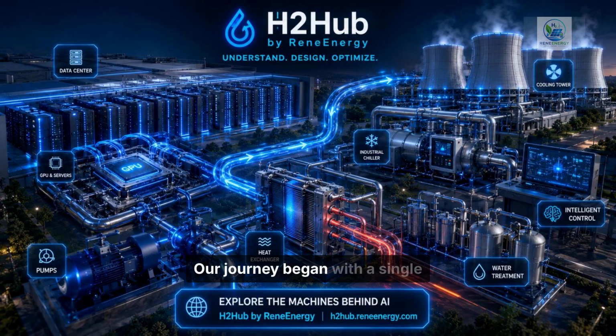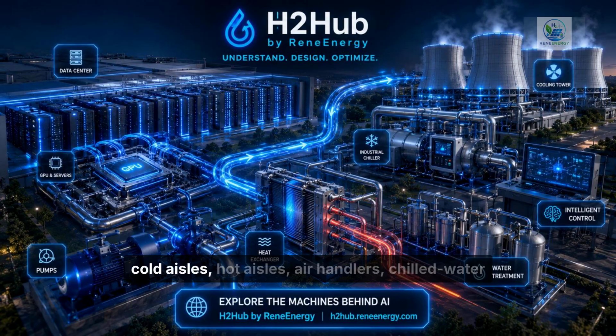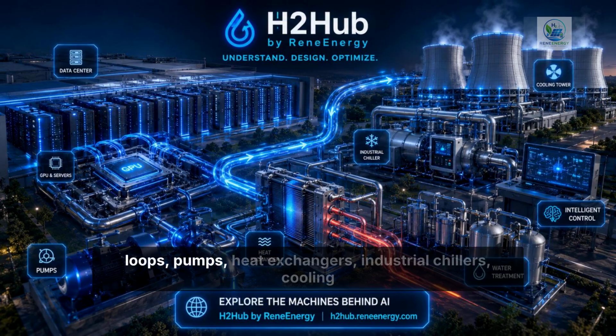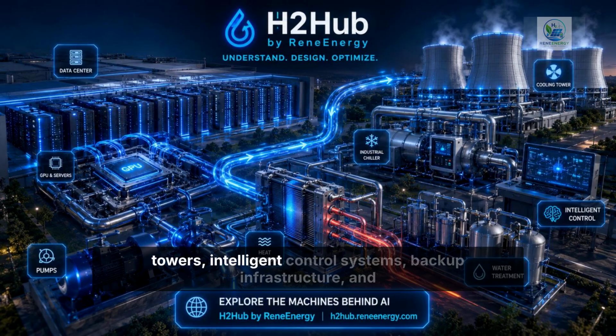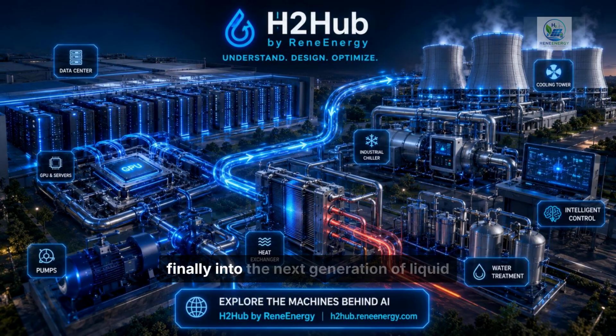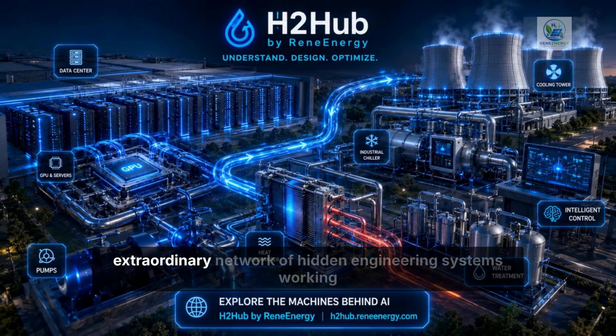Our journey began with a single AI processor generating heat. We followed that heat through server fans, cold aisles, hot aisles, air handlers, chilled water loops, pumps, heat exchangers, industrial chillers, cooling towers, intelligent control systems, backup infrastructure, and finally into the next generation of liquid cooling technologies. What appears to be a simple AI response is actually supported by an extraordinary network of hidden engineering systems working together with remarkable precision.